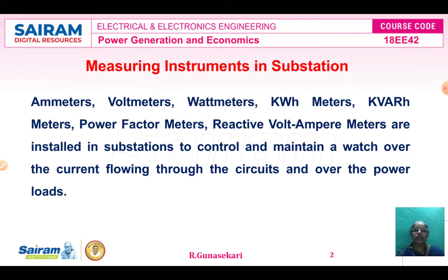kVARH meters, that is kilovolt ampere reactive hour meters, which are used for measuring the reactive power energy. Power factor meters, used for measuring power factor. Reactive volt ampere meters, used for measuring reactive power. All the measuring instruments used in the substations are installed to control and maintain watch over the current flowing through the circuits of the substation and over the power loads of the substation.